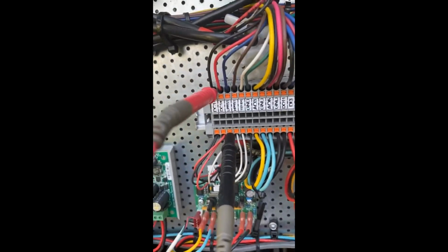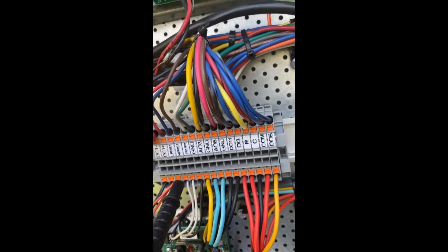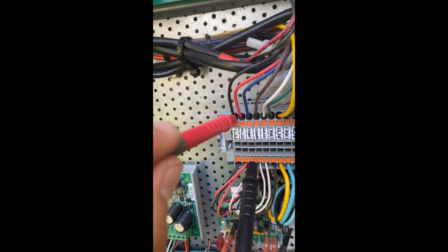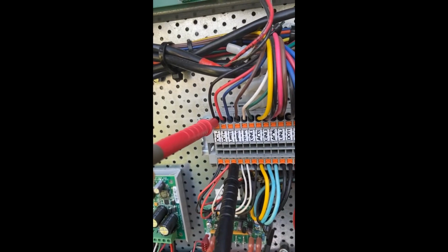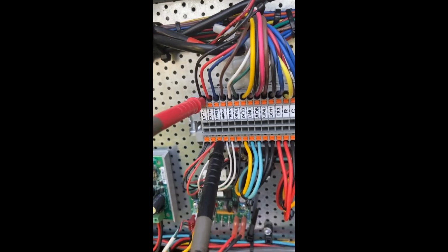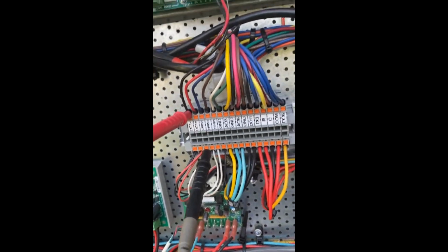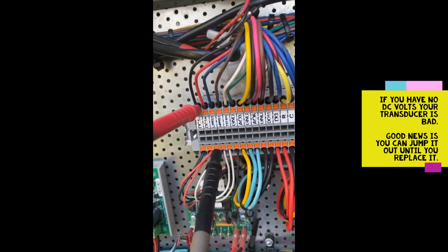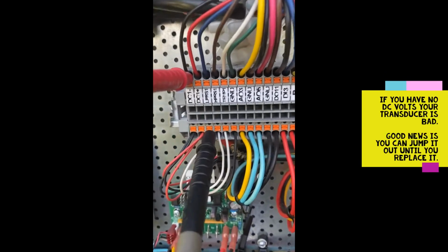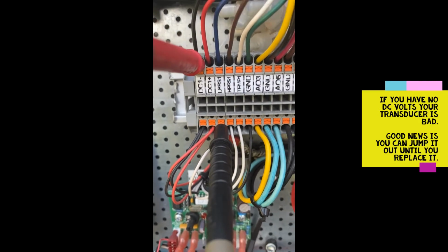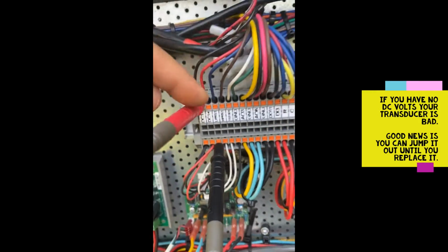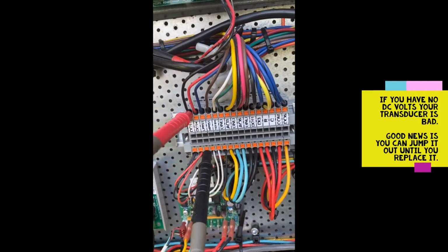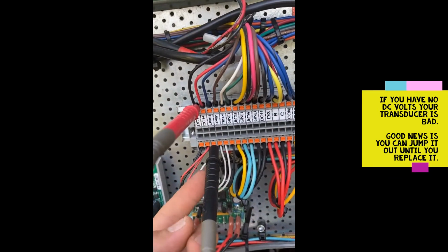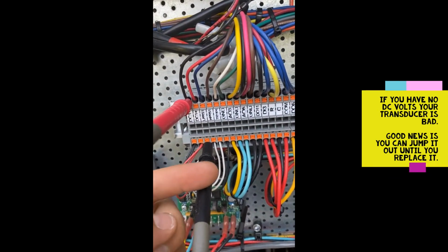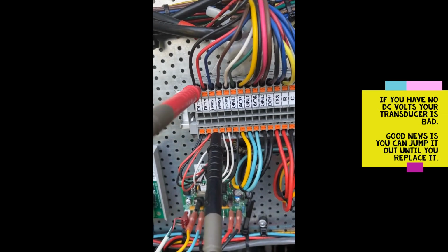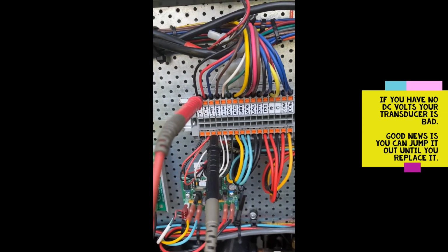So you see I'm keeping my lead here. You can do either one, positive or negative. All you're gonna do is get either a negative or a positive number. Like right now I have a negative number, not a big deal, as long as you see that it's more than a volt. So I stuck my other lead on the low pressure, which is for the transducer. So this is telling me voltage is coming in from the board through the transducer, coming back out this way. And if I have no voltage here at all, the transducer's not sending any. You should have at least half a volt on this type.